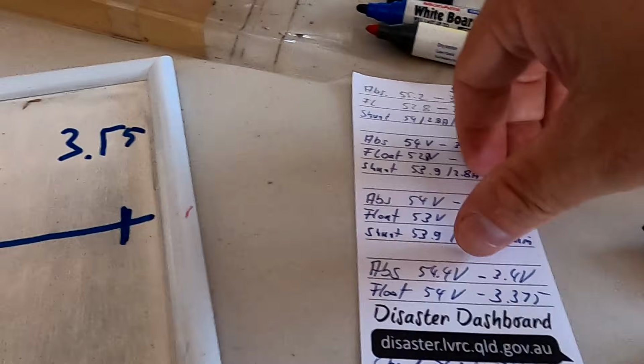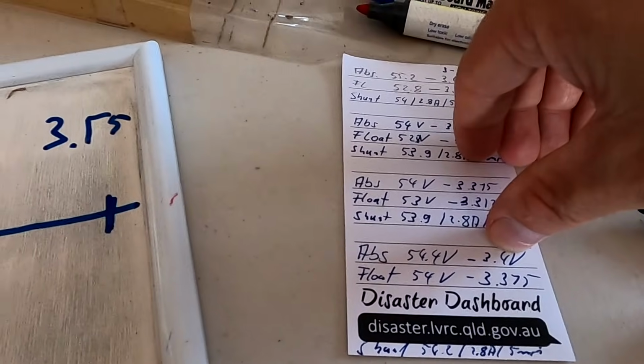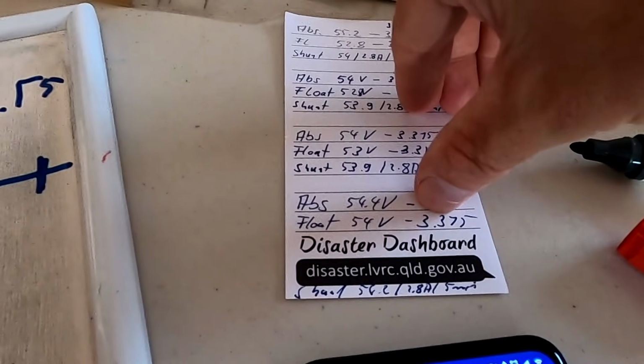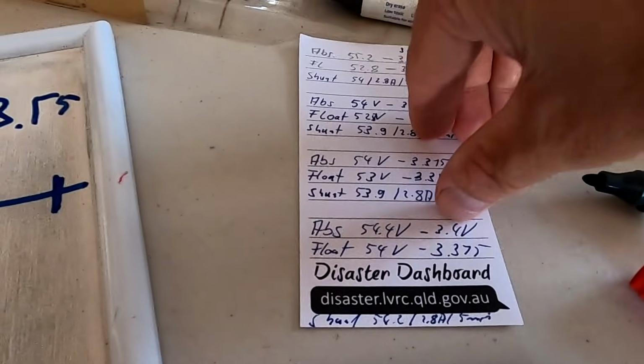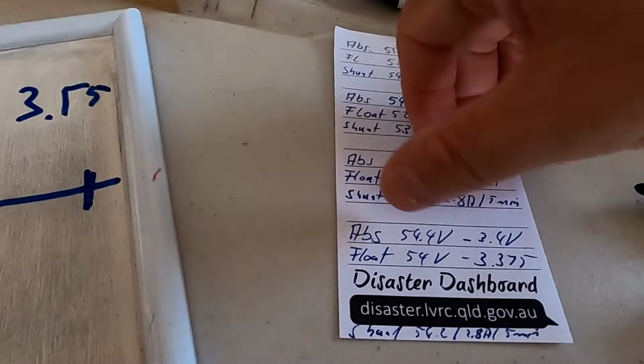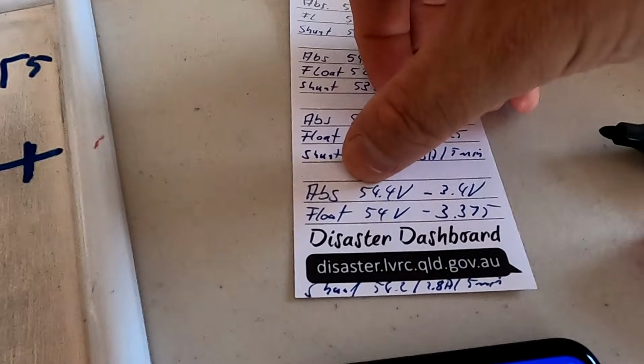At the moment I've got this set to 3.4 volts per cell, and the float is on 3.375, just underneath this 3.4. So overall the charge controller should charge to 54.4. It tried to do this before but couldn't, because some of the cells were already peaking past 3.5 volts, so I had to push them down using my light bulbs and everything to discharge these cells. There were more and more cells peaking the fuller the battery bank got, and there was a moment when I turned everything off and said, no, that's too much now, it's not working.